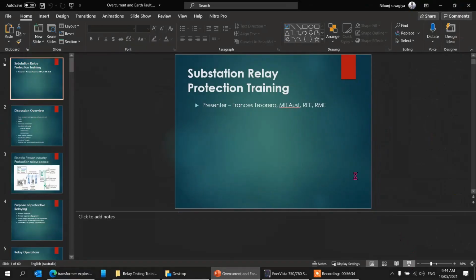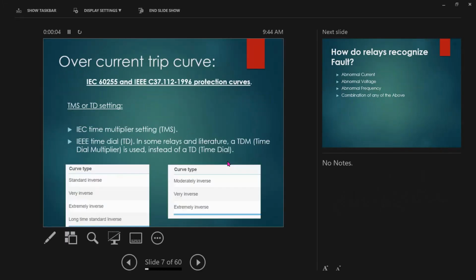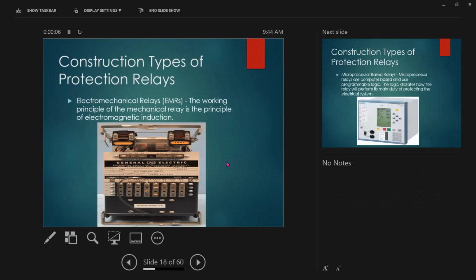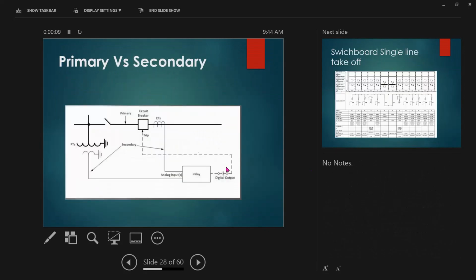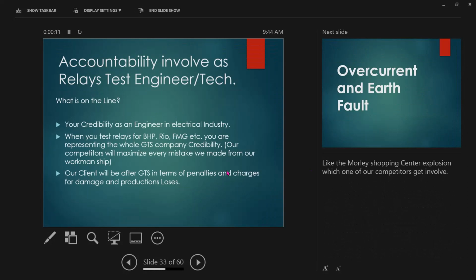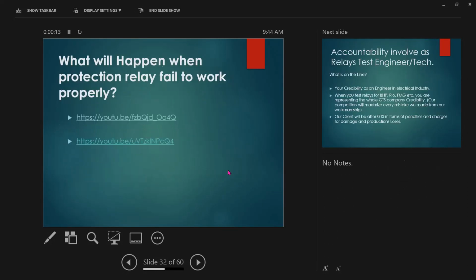Anything that we have discussed. Short circuits, and many things will work in there. Buchholz will work, your oil temperature, winding temperature trips, nothing works, isn't it? If those inputs went to your relay, probably the relay didn't give an output to your breaker, and if the relay gave an output to your breaker, probably the breaker didn't work. Maybe the breaker is faulty. Or the interface didn't work. Correct. So many things. It could be, yeah, you're right.